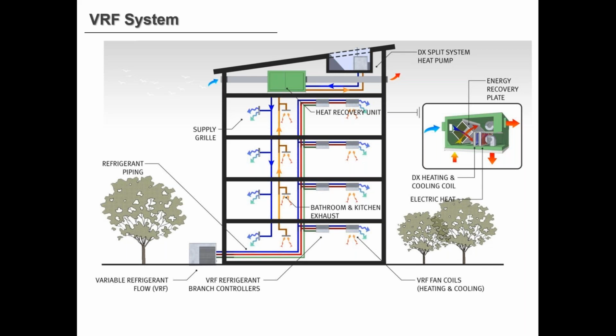So refrigerant piping is much more efficient at transferring energy through your building as compared to some of the older building infrastructure where you have a rooftop air handling unit, for example, that delivers all of its energy on the air side and none of it through either a water or a refrigerant side. So the decoupling is very good. It allows us to control ventilation and where it goes. It allows us to get energy recovery, more importantly, off of that outdoor air. And then it allows us to control the temperature in those rooms separate from the air side.